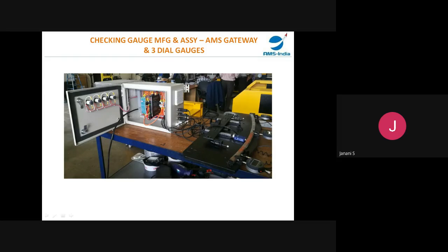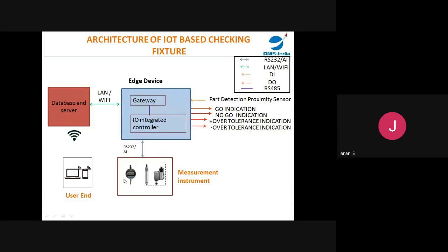If the measurement is within the tolerance range we have programmed, you get a go or no-go indication. Here I'm measuring it through RS-232 protocol, sending it to a device with an inbuilt controller, or a separate controller that I can later link with the gateway. If the communication happens and my program runs, it tells go or no-go based on the tolerance I've set. Beyond the expected range doesn't always mean rejection.